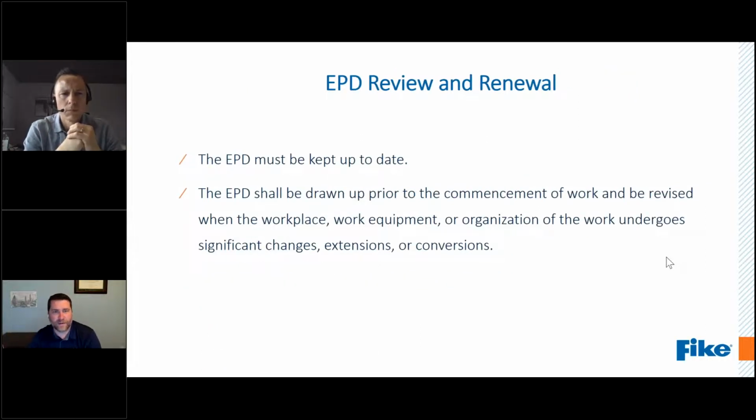And finally, we've got the EPD review and renewal or revalidation. So the EPD must be kept up to date. This should be considered like a living document. It needs to be drawn up prior to the commencement of work, and then you revise it as anything changes that impacts it. So if you're changing the workplace or the equipment, process changes, material changes, things like that, this needs to be updated as part of that.